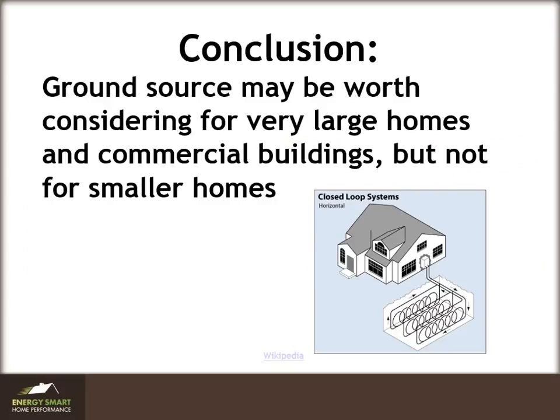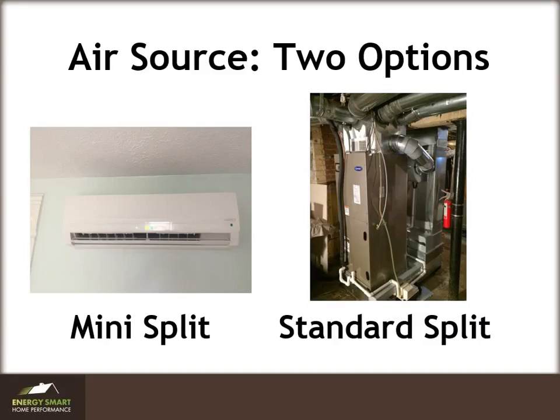All right. Yeah, that totally got messed up. So the ground source heat pumps, where they do make sense and pencil out, if you are honest about the math, which unfortunately almost no one in my world is genuinely honest and tracks to see what happens to the actual energy use after the fact. If you're honest about the math, if you don't have a 5,000 square foot house and up, geo probably doesn't pencil. It just doesn't. If you have a big commercial building like this, geo can actually do fine too, but you need a lot of energy use and a lot of space before the math starts to work. So I'm sorry to beat up on geo, but we've done the math. It's just kind of where it is.